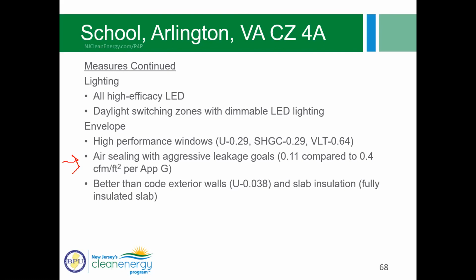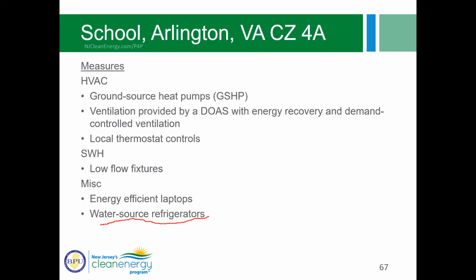So the takeaway here is there are some commonalities, right, with these high performing buildings. So we see a lot of direct outside air, I think every one of these had a direct outside air unit with energy recovery. So the outside air was decoupled from the systems that provided the heating and cooling. Demand controlled or natural ventilation, high efficacy lighting. Then an effort to maximize lighting controls was also present in all of these strategies. High performance windows, low flow plumbing fixtures were present in all of them. And the big one, heat pump HVAC systems. So the hotel had VRF. The office, I believe, had a ground source heat pump system. And then the school also had a ground source heat pump system. So yeah, all heat pump systems.